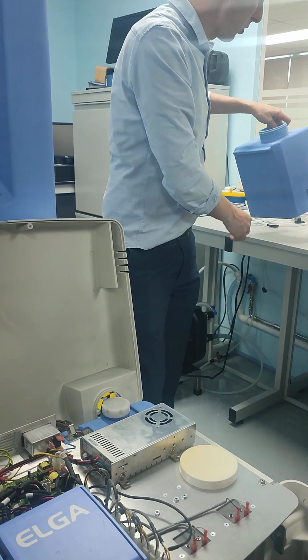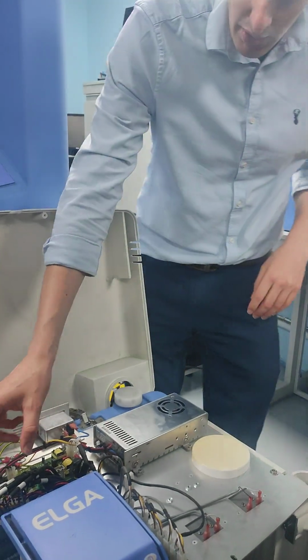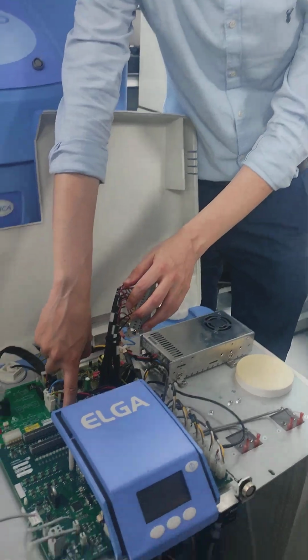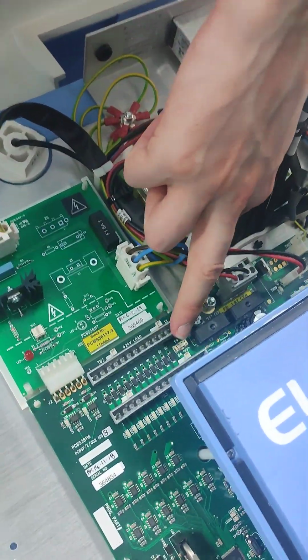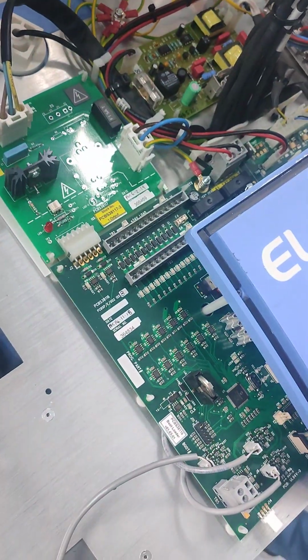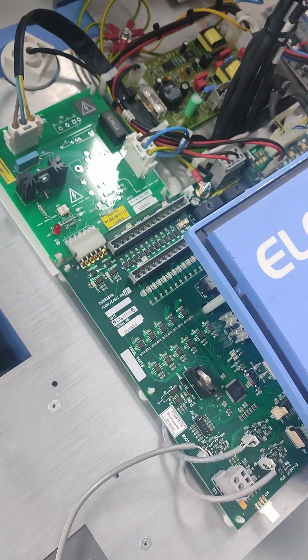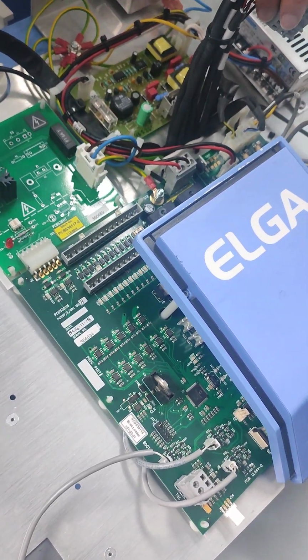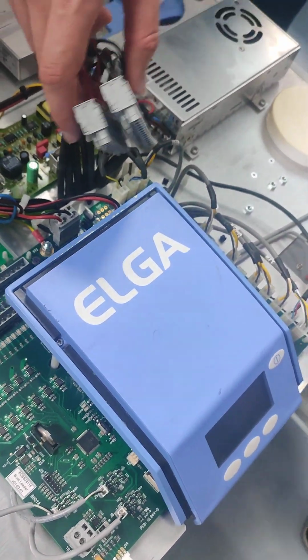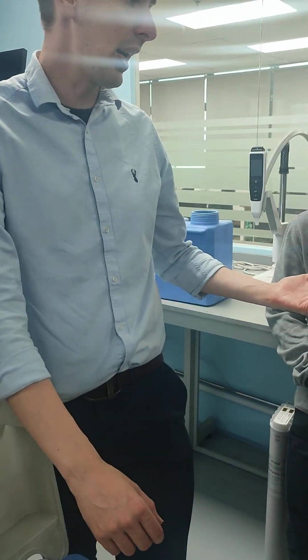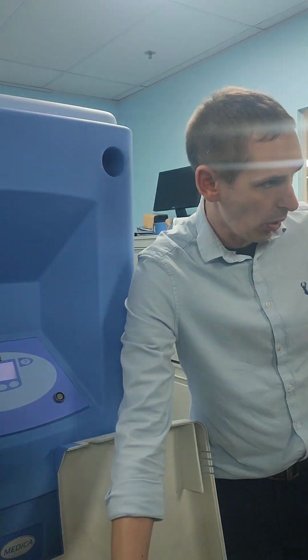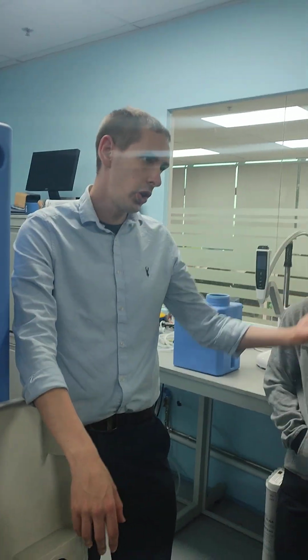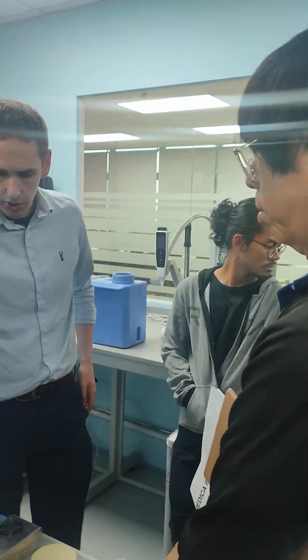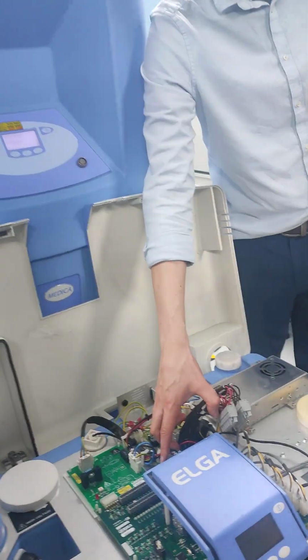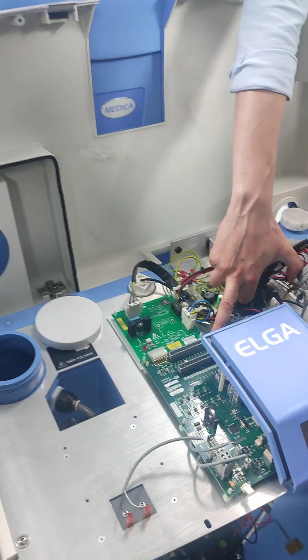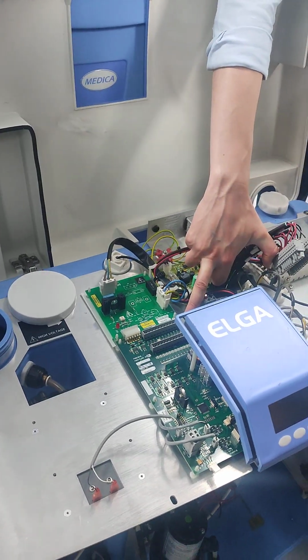On this one we also have some fuses. We have a small 5 amp micro fuse, which is for the recirculation pump. What you often find when they leak, like this one did the other day, it can quite often take out the micro fuse. So if you put a new one in and it still doesn't work, your first check is that micro fuse, which is the same as what's on the Flex and Chorus.